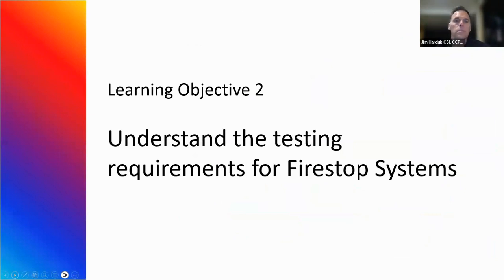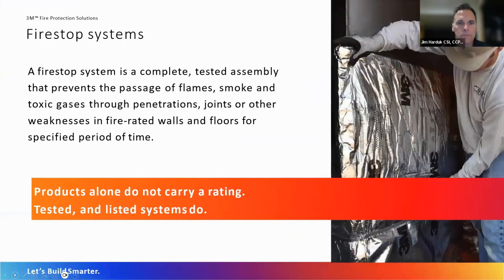So now I want to talk a little bit about some of the testing requirements for fire stop systems. Next slide. So this is probably the most important slide in this presentation. When we're talking about fire stopping, we're actually talking about a system. It's a complete tested assembly that prevents the passage of flame, smoke, and toxic gas through a penetrating item or through a joint or any other kind of weakness in a fire-rated floor or wall assembly. And this is for a specified period of time. It could be 1, 2, 3, up to 4 hours.